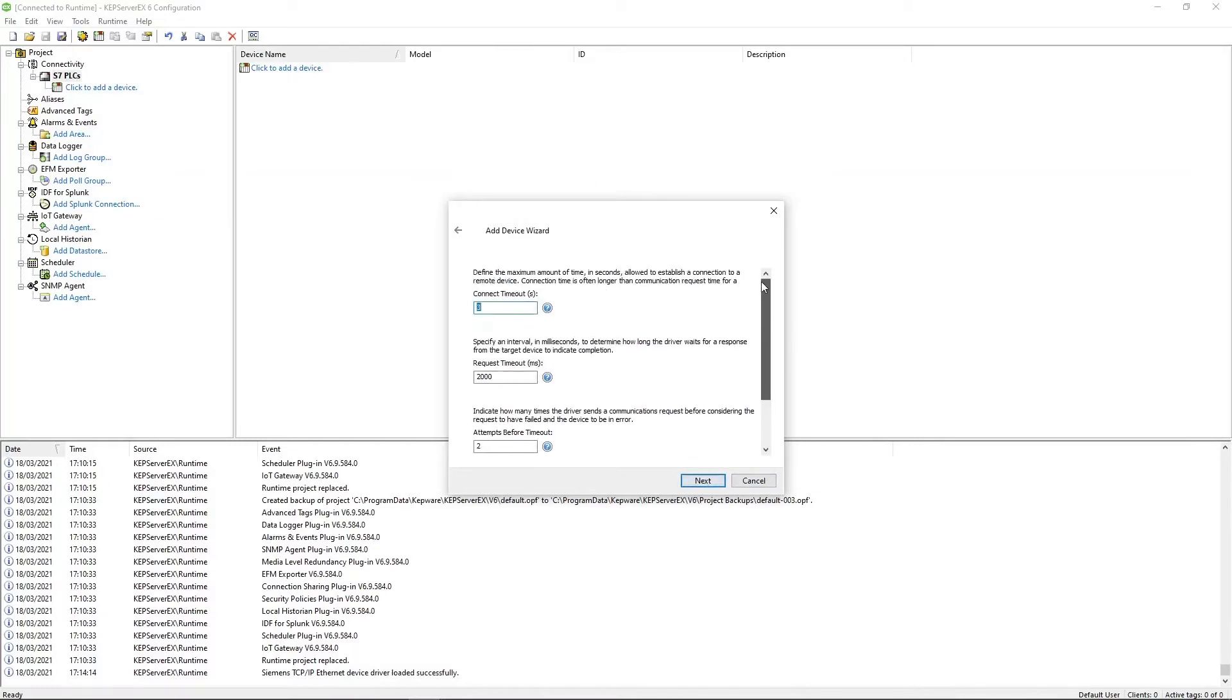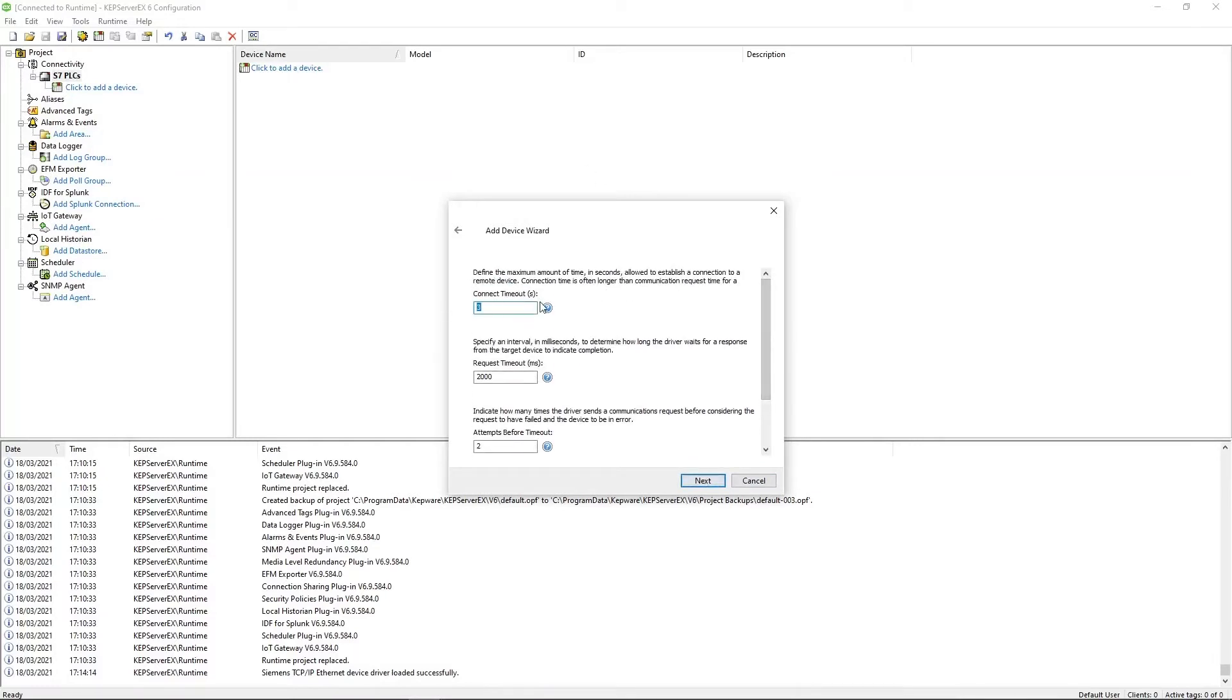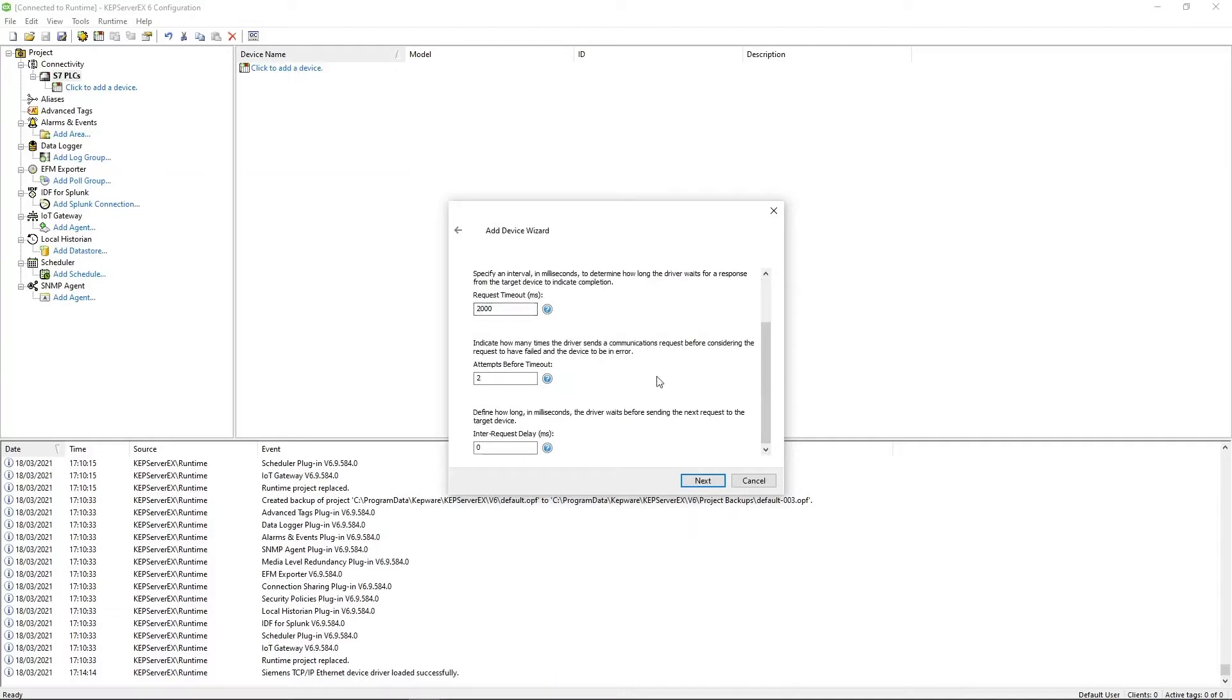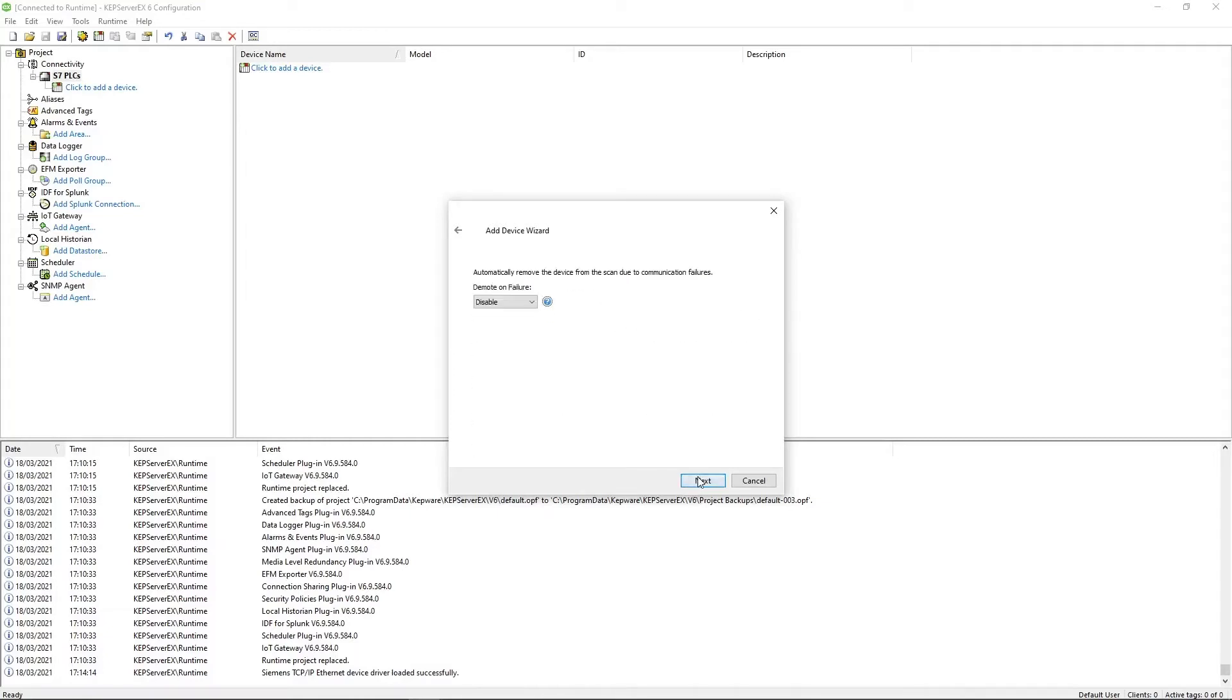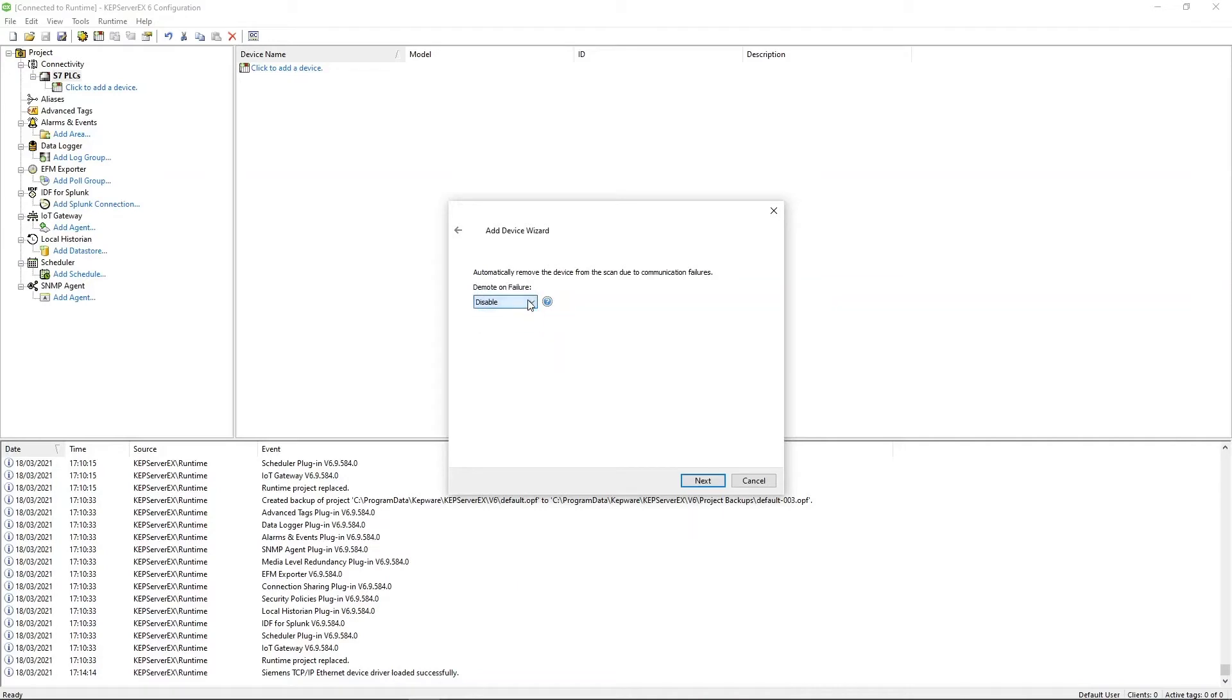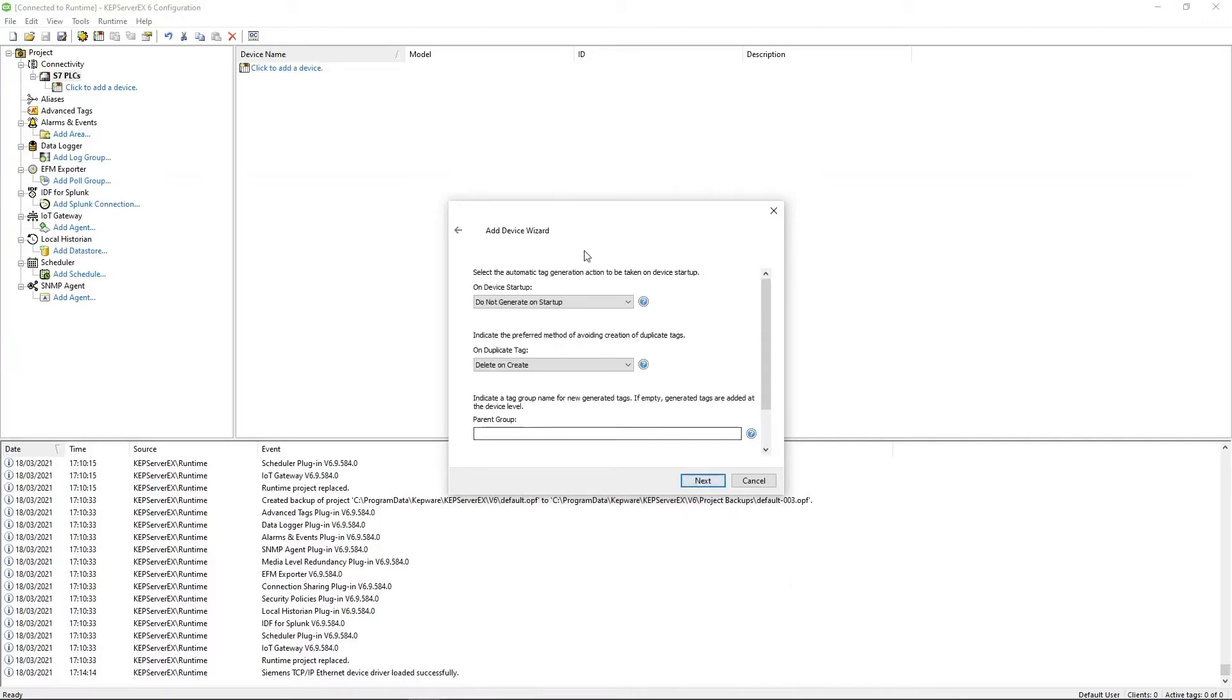These are connection timeouts and request timeouts. Important values. I'm going to leave this all at default, but depending on your network setup and how often and how long it might take for replies to return, you may need to change these values. But for these purposes, I'm just going to leave these all at default. And again, if you can't connect to the PLC, this lets you choose what happens. Does Kepware continue just constantly trying to reach out to the PLC or does it demote and put it on a timeout? So I think it's 10 seconds is the default where it'll wait 10 seconds before trying to pull again. Next.